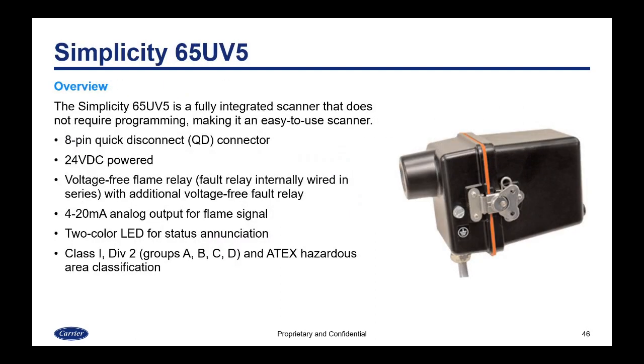These are our FireEye integrated scanners. First is the Simplicity — a fully integrated scanner that does not require any programming, making it very easy to use. It has an 8-pin quick disconnect connector, is 24 volt DC powered, and has a flame relay and a fault relay. It provides a 4 to 20 milliamp analog output for the flame signal, a two-color LED for simple status annunciation, and is Class 1 Div 2 and ATEX hazardous area rated.